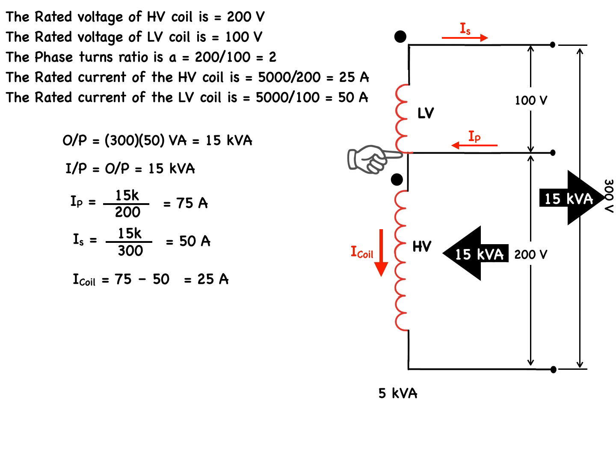No matter whether the two-winding transformer is used as a two-winding transformer or as an autotransformer, MMF must be balanced in the coils. If the current comes out through the dot terminal of the low voltage coil, current must flow in through the dot of the high voltage coil. It is important to note that as a two-winding transformer, kVA handling capacity is 5 kVA, the rating of the transformer. However, the same transformer, when connected as an autotransformer, has a kVA handling capacity of 15 kVA without overloading any of the coils.